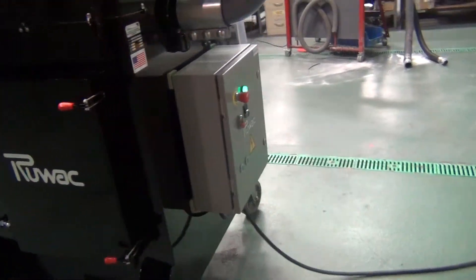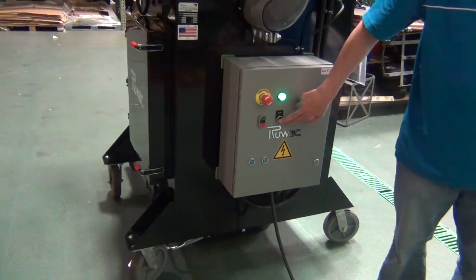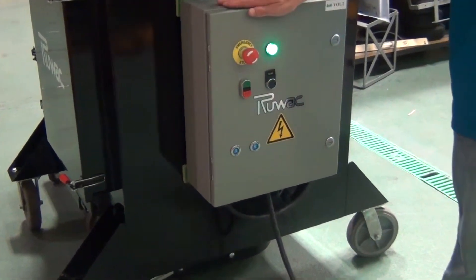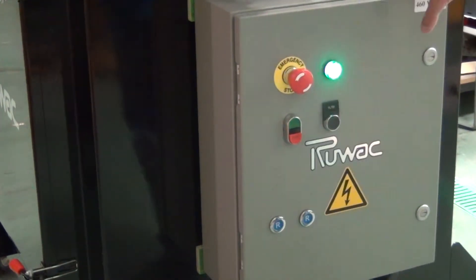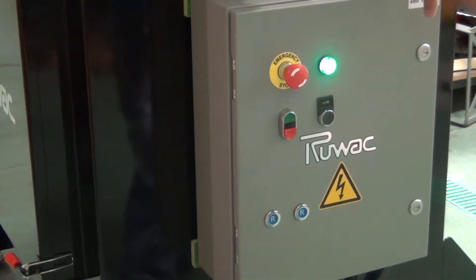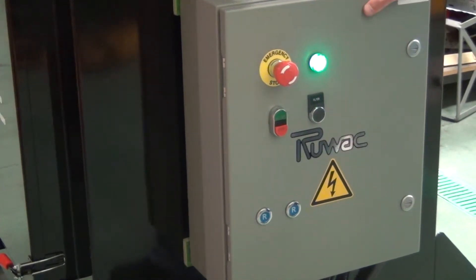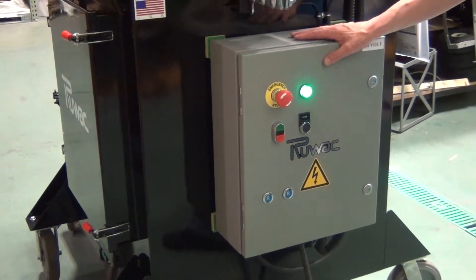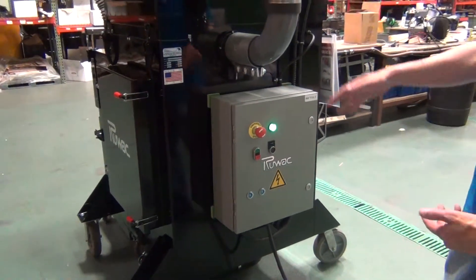Simple control panel. It has an emergency e-stop, a run light, a momentary button for the filter, and reset buttons on the outside so you never have to open it up should you need to reset it for any reason, and an on/off button. This unit is also equipped to run off a remote starter — you can hook it up to a low voltage 24 volt system. It's already pre-wired for that and you can run this from an external system up to a thousand feet away and turn the vacuum on locally or turn it remotely.